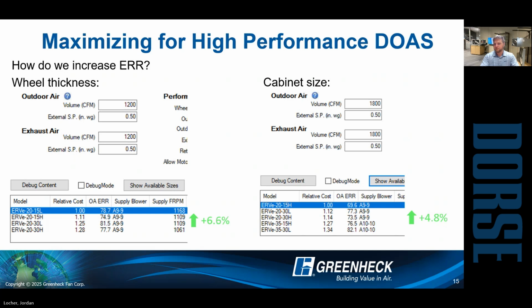You might have chosen the larger unit because you wanted the effectiveness, but if another manufacturer or another rep or vendor comes in and supplies a code minimum equivalent, whereas we, as Dorse and Greenheck, are trying to bid what you intended with the larger model, we would undoubtedly potentially lose out on a project to somebody bidding a smaller, less efficient, less effective, cheaper unit. So we always say schedule what you want: schedule the model number, schedule those effectiveness values as the absolute minimum. And the most important thing we always say on the rep side of the business is hold your spec in that regard. So I just wanted to throw that in there, Jordan.